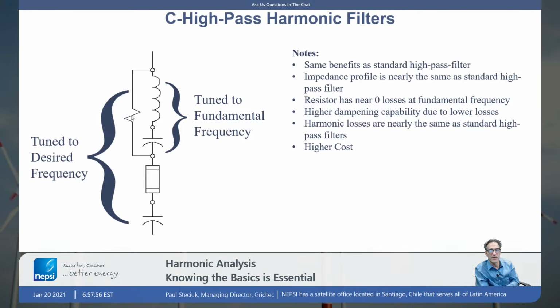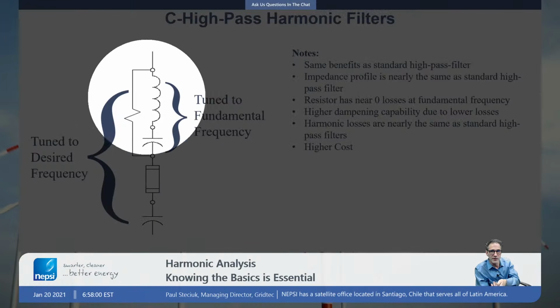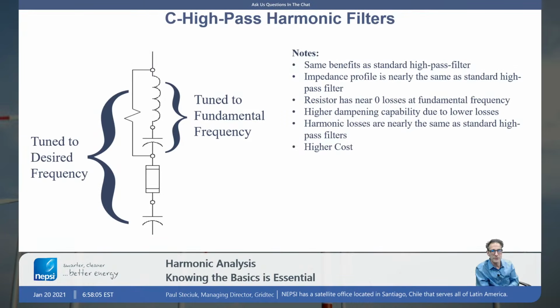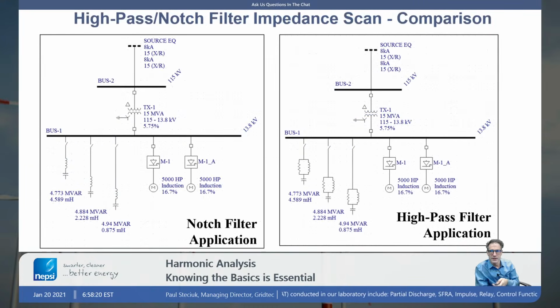What we're doing is we're eliminating the impedance across that resistor, which then eliminates the power losses within the resistor. If I have 0 volts, because X of C equals X of L here at that fundamental frequency, it means I have no losses. It means I can bring my resistor value to a very low value, so I would say high damping of the filter, and flatten out that curve and eliminate those resonance concerns that we pointed out earlier. So we're about ready to complete here.